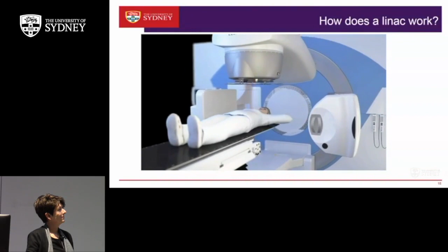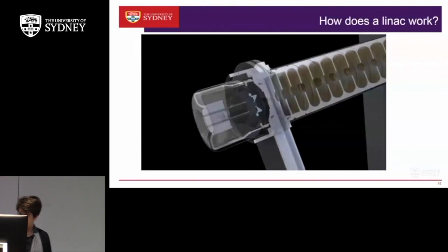Beam generation. Radio frequency waves are pulsed into the waveguide by the magnetron. This is synchronized with the injection of electrons into the waveguide by the electron gun. The radio frequency waves accelerate the electrons along the waveguide to a speed approaching the speed of light. The X-ray beam is created when the electrons hit and interact with a tungsten target at the opposite end. The magnetron controls the power and frequency of the radio frequency waves, which determine the energy of the X-rays produced. The digital accelerator uses a diode-type electron gun situated at the end of the waveguide. The electrons are produced by heating the tungsten filament within the cathode and are then injected into the waveguide. The number of electrons injected is controlled by the temperature of the filament.